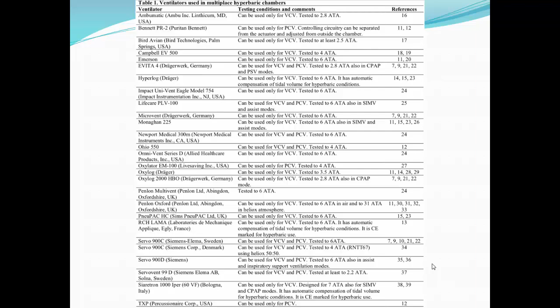It's interesting. The Navy actually looked into this, and they used the Penlon Oxford ventilator, which is certified for use in the Navy chambers, but in the early 80s they stopped making that ventilator. They couldn't find the repair parts, and so they did studies on their own, looking at all the modern ventilators to see if they worked in the Navy hyperbaric chambers, because they wanted to keep pushing their Navy divers and be able to provide treatment to them if they were harmed by gas embolism or decompression sickness in whatever environment they were at. And so they ended up coming up with 4 ventilators that are approved by the Navy and used in the Navy chambers. The Univent Eagle is one of them. So despite the one FDA-approved ventilator, there are 4 other ones that the Navy uses.